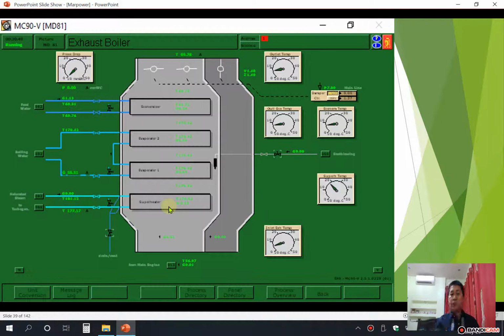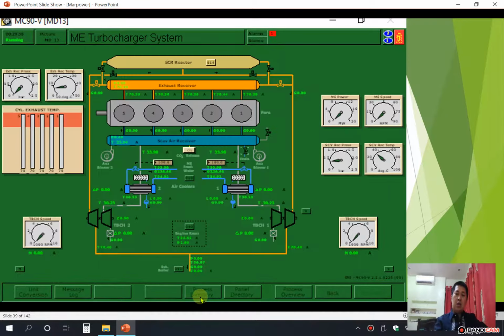So this is waste energy recovery. The heat of your exhaust gas will heat the boiler water to produce steam. Your exhaust gas will then flow to the exhaust pipe to the atmosphere. So that is the waste recovery. There is a damper here. If the temperature of your boiler water reaches normal temperature, the damper here will open and the damper here will close, so the exhaust gas will flow here to the exhaust pipe going to the atmosphere. So that is the waste energy recovery.